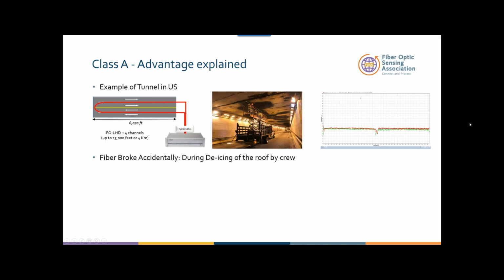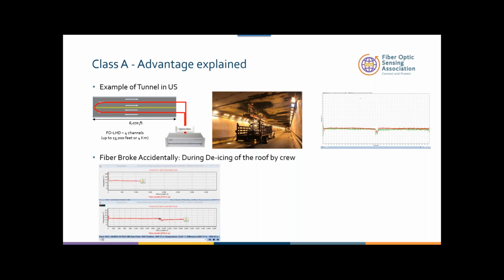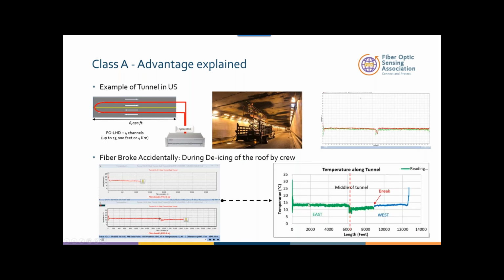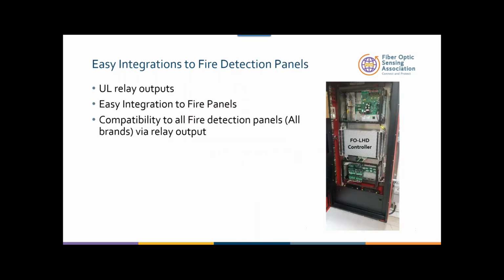Because of de-icing a year ago, these gentlemen used certain tools to remove the ice from the ceiling in these tunnels. Unfortunately, they broke the cable. The beauty is that the software detected a fiber break and gave an alarm. At the end of the day, we still monitor the first lane, eastbound, and the westbound, and you only lose so much coverage, which is probably 1 or 2 meters. That is the beauty of fiber optic linear heat detection.